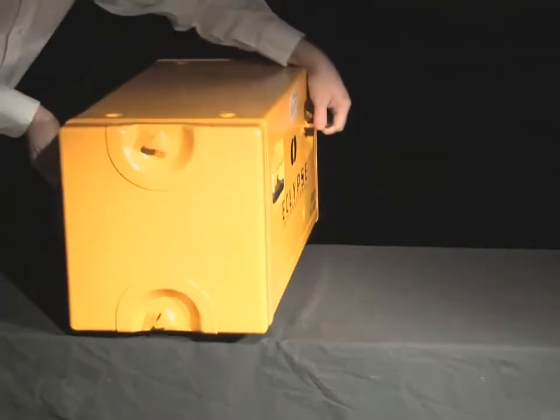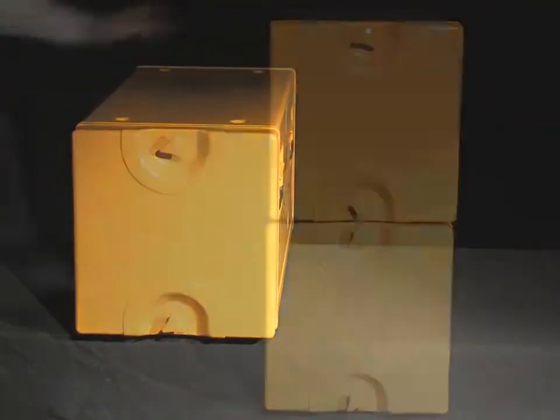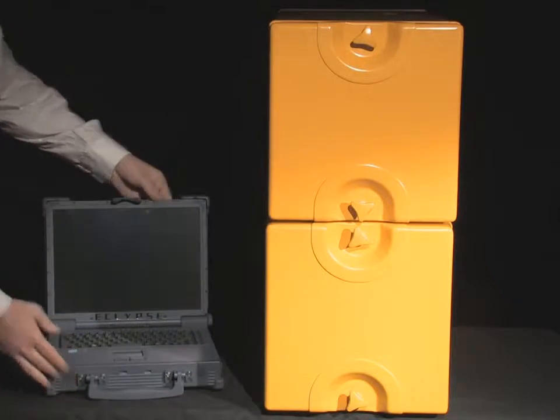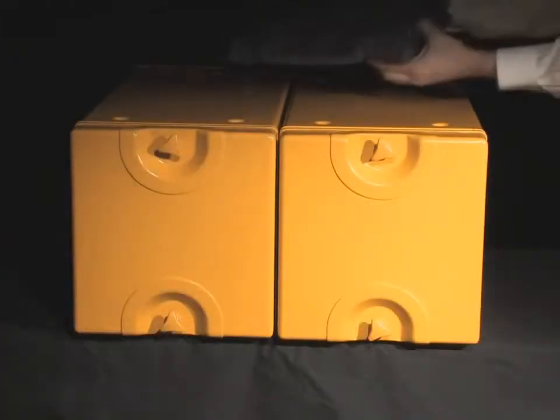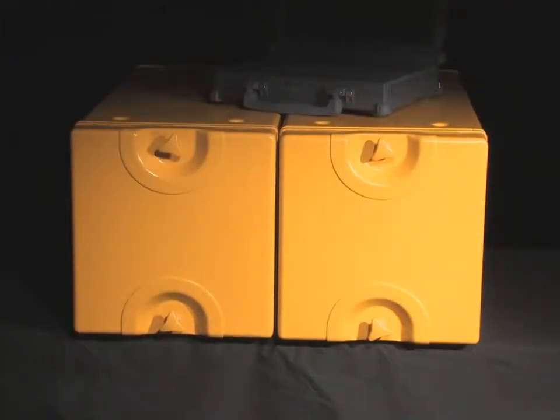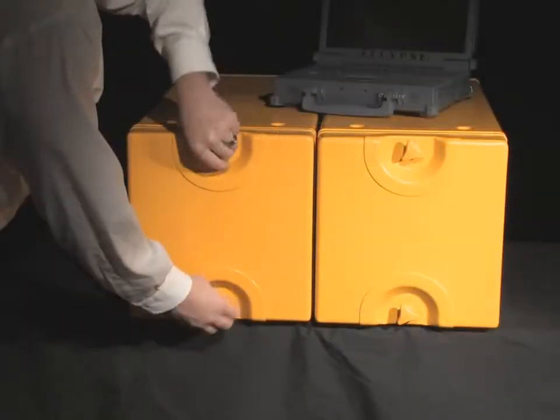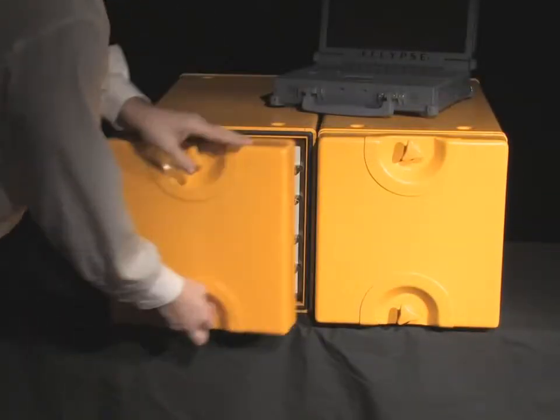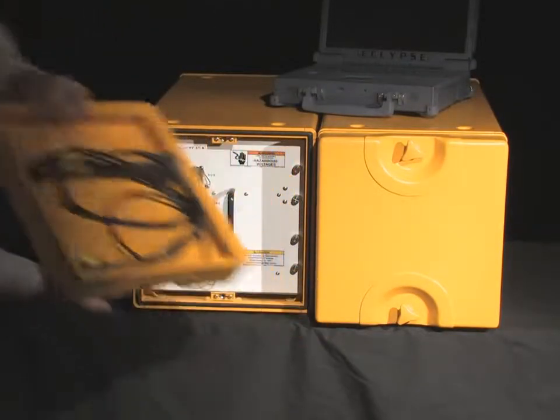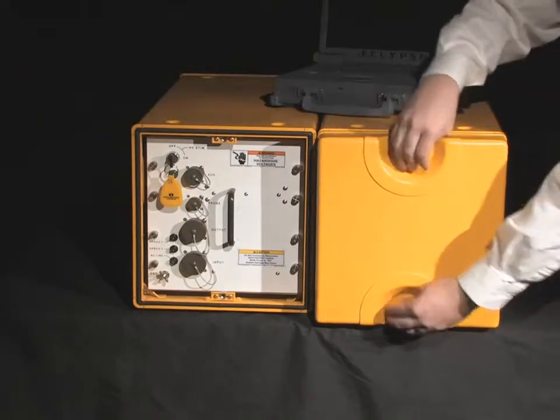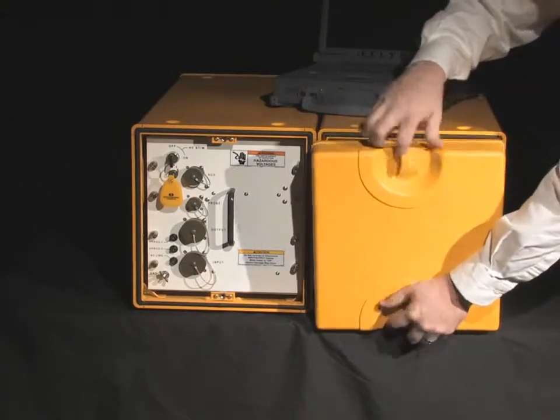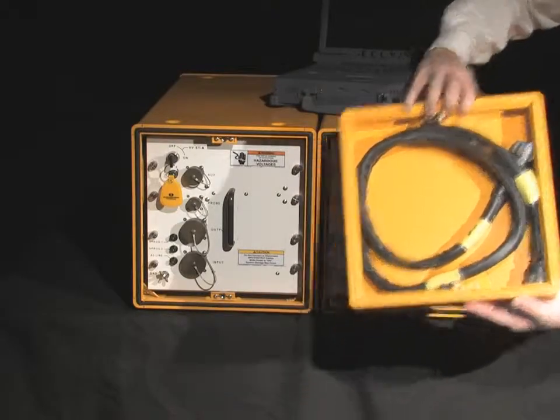First, select a location and an AC power source. Arrange the equipment where the testing is to be performed. Equipment may be stacked for use in areas with limited space, or it can be spread out for testing larger units under test. Remove covers from all units by loosening the top and bottom fasteners of each cover and set them aside. If present, remove any cable assemblies that may be stored inside the covers.